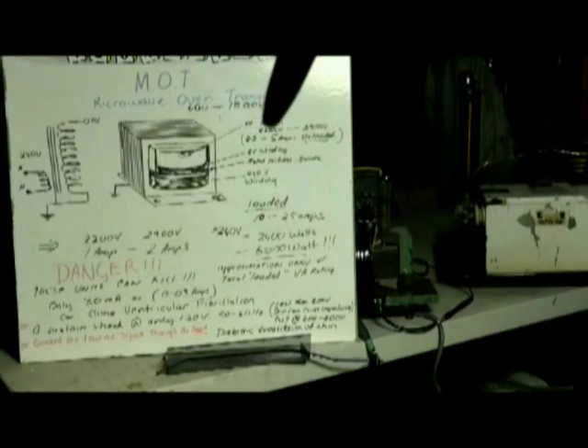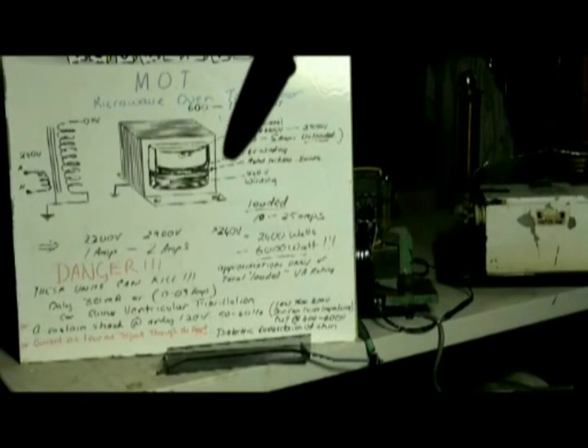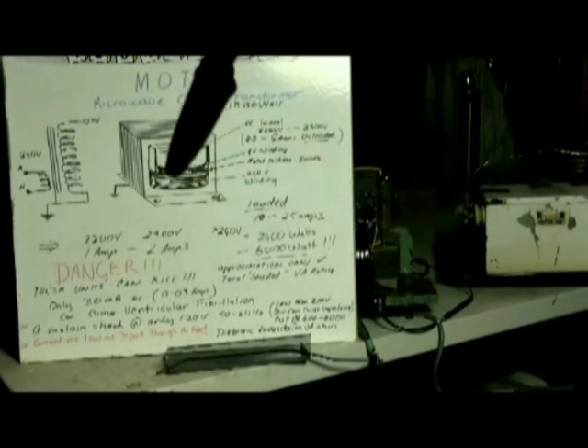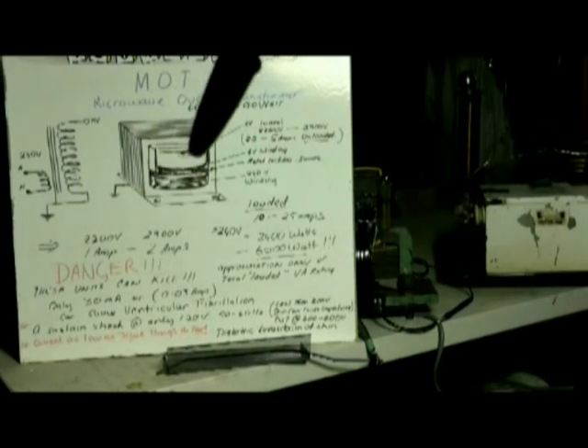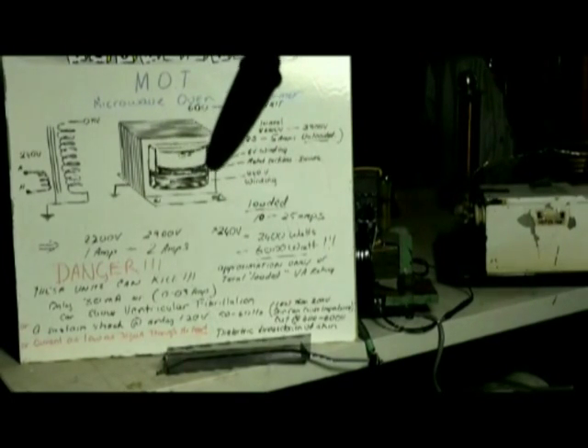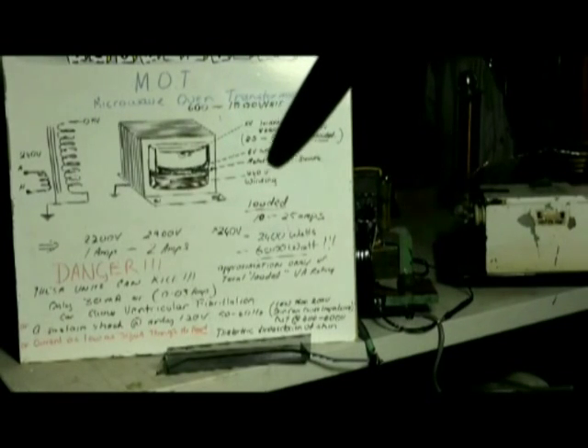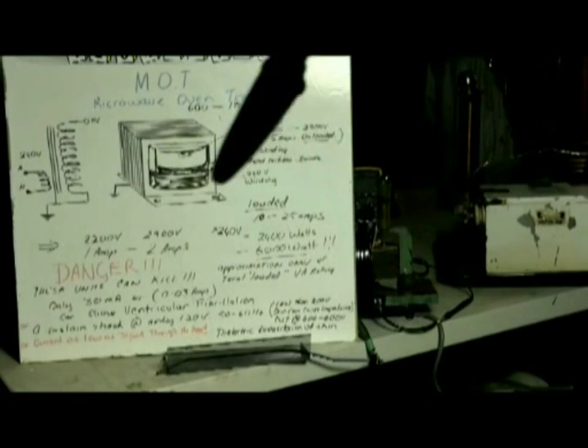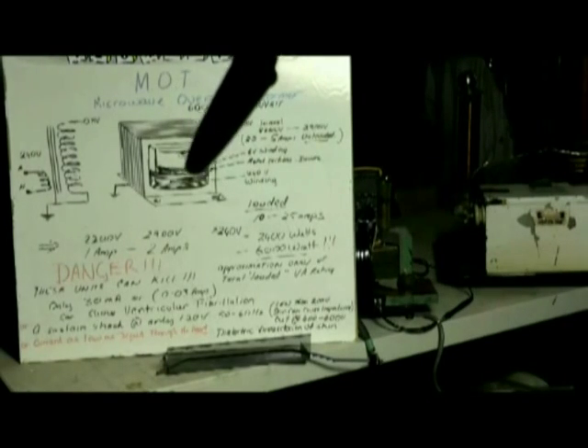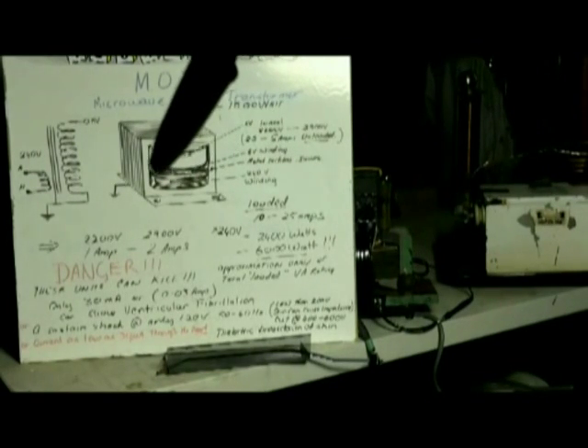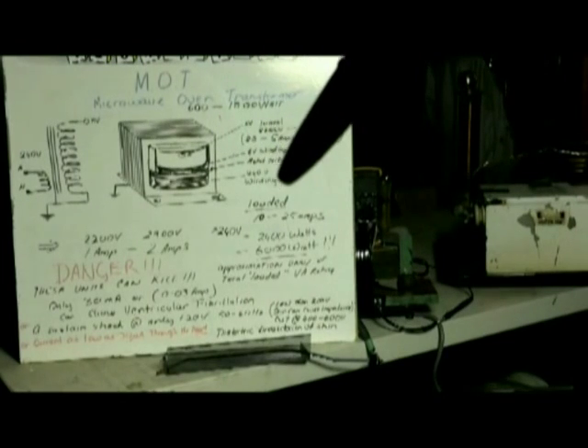These have been tested, or the ones I had here, between 600 to 1500 watts. The voltage on the high voltage terminal ranged from 2200 all the way to 2900 volts. Their unloaded current drew 2.5 to 5 amps. There's a 6-volt winding tucked in there, but we're not interested in that, so it's not necessary for this presentation. There are metal sections or shunts inside there which we can leave alone because unless you're planning to dismantle them, they're probably best left alone.